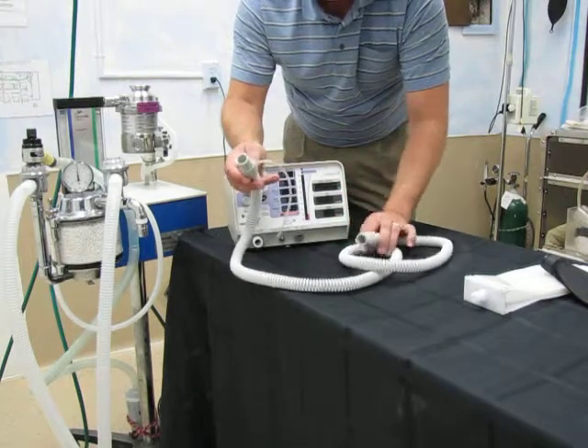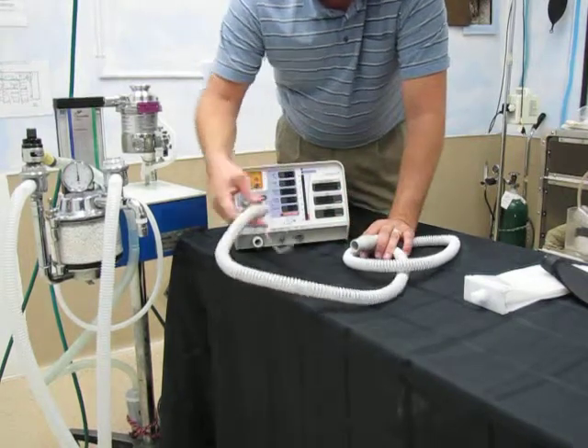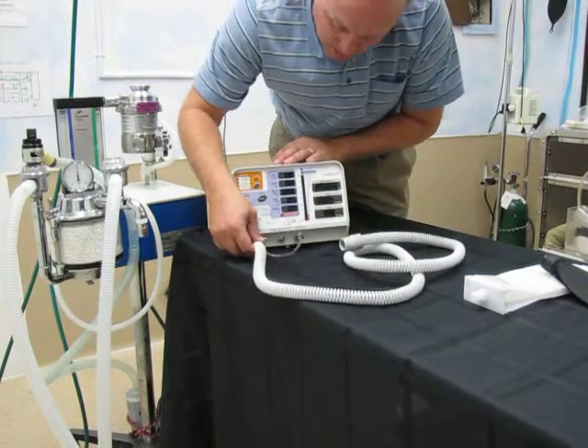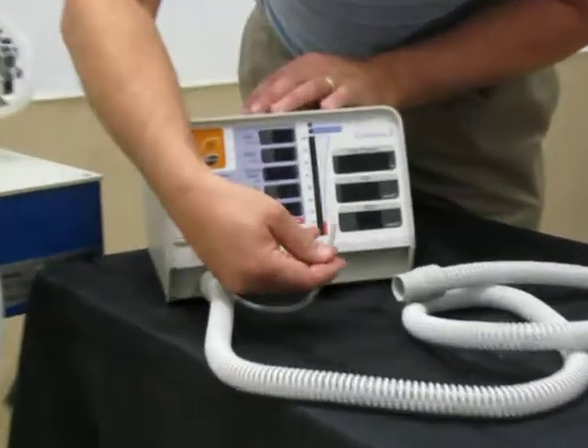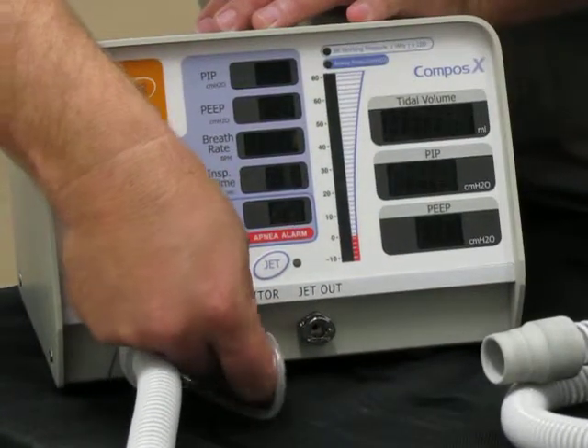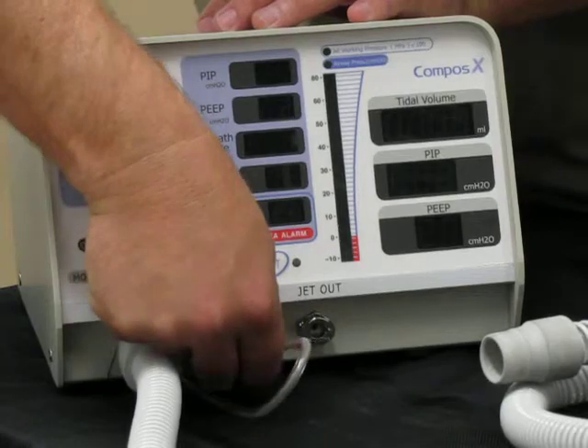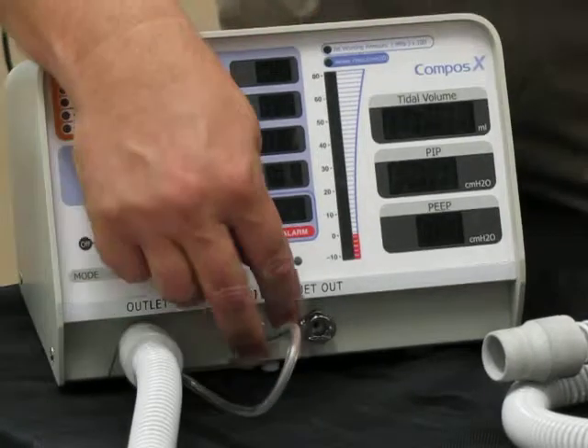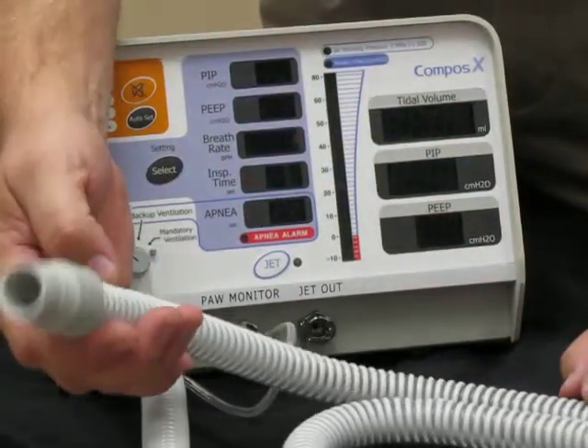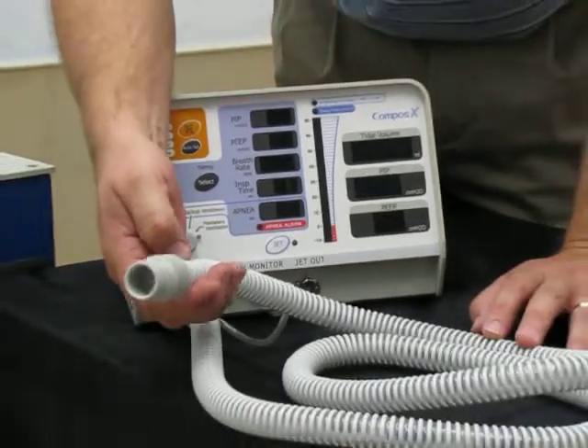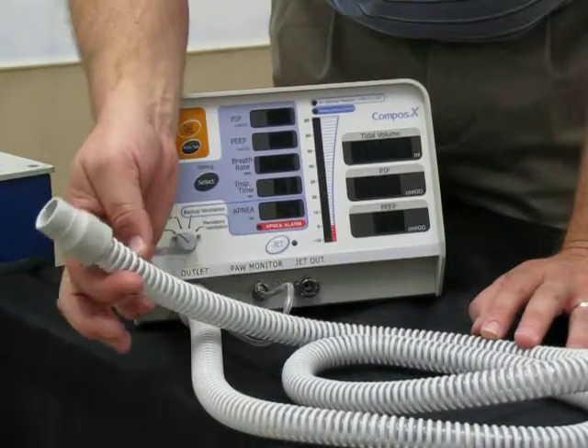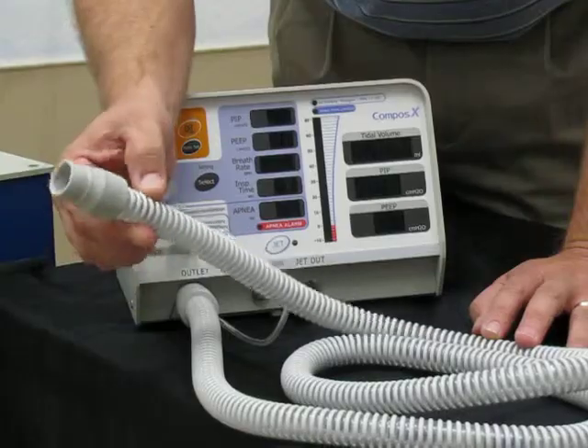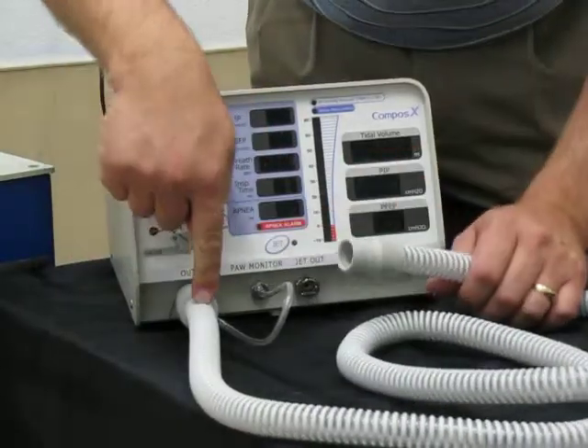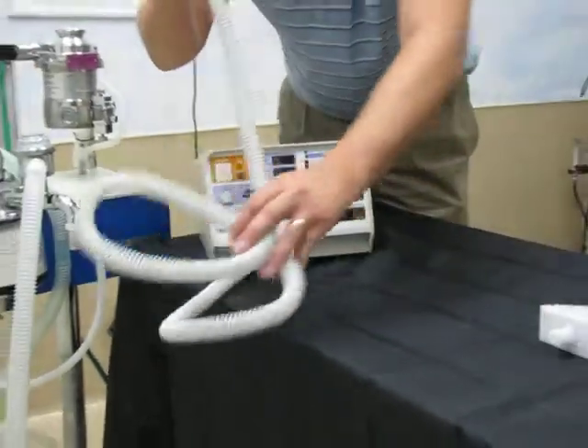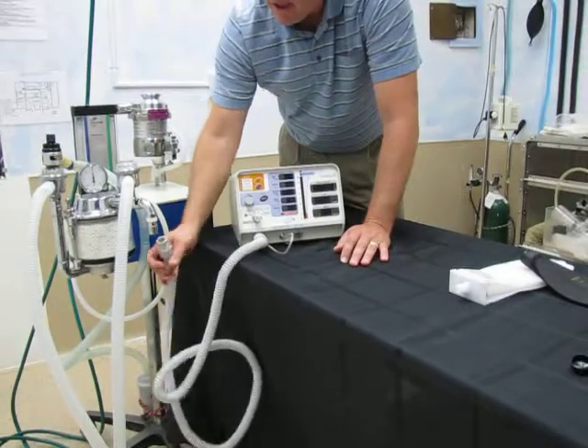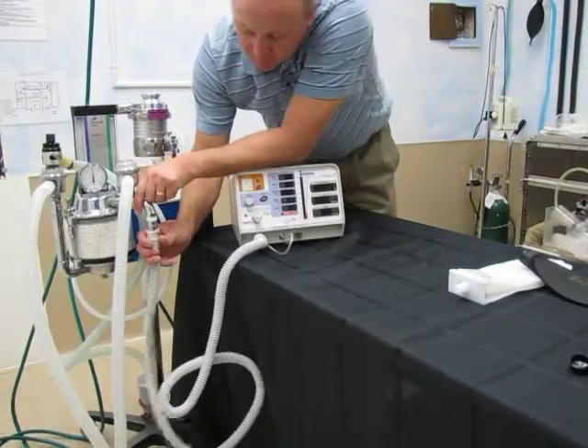This end goes to the ventilator, and we hook this portion to the patient port, and this to the pressure port, and this is your pressure monitor. And this tube actually runs all the way up to about here on your tube, so you're actually reading the pressures at this point rather than way down here. And then we're going to hook this up to the bag port on the anesthetic machine.